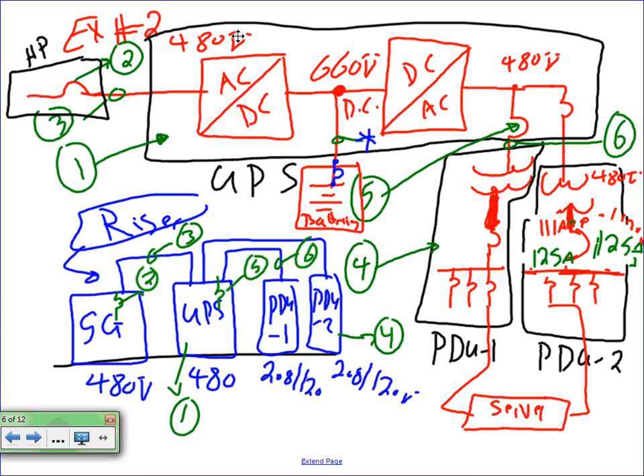So this is your bank of batteries, typically for 15 to 20 minutes worth of power at full load. It will power all your system here for probably 10, 15 to 20 minutes. Then out of here, they invert from DC back into AC, because we burn everything at AC. They have some type of distribution section inside the UPS system, and from here they feed multiple PDUs, PDU1 and PDU2.